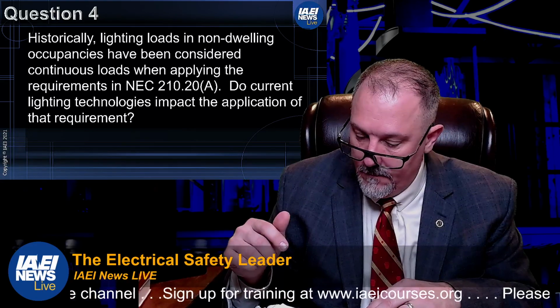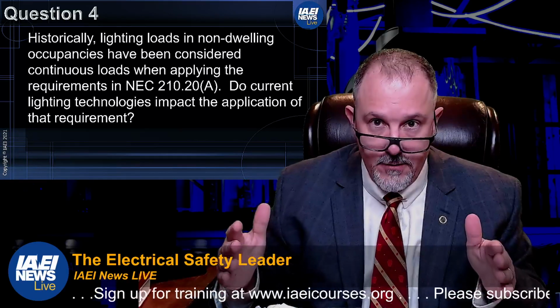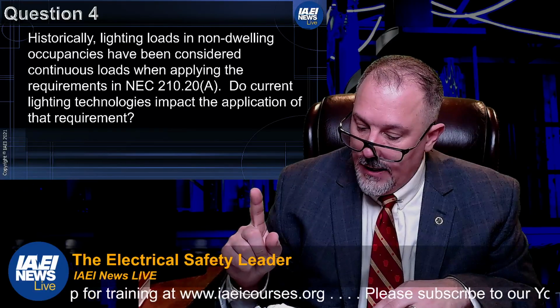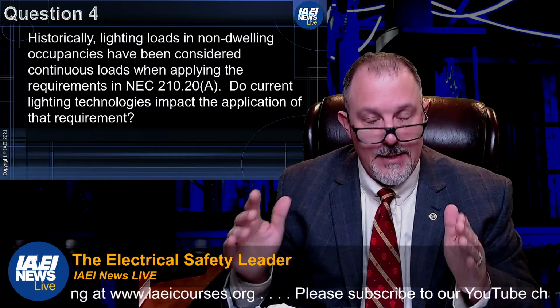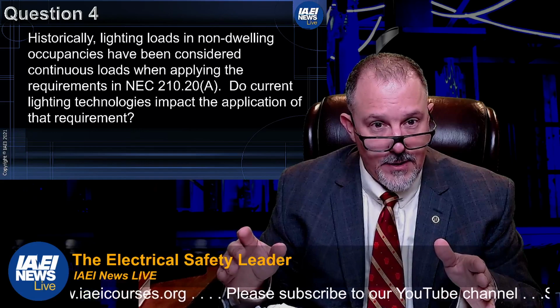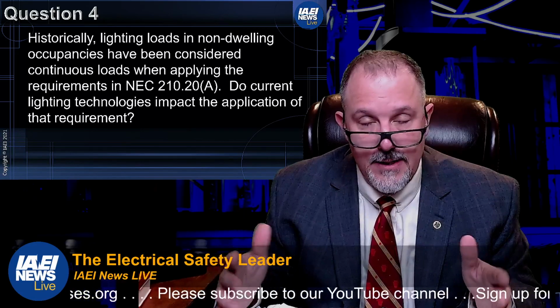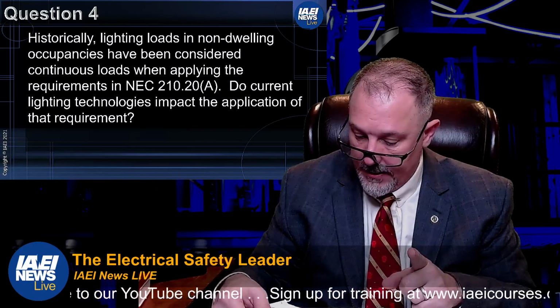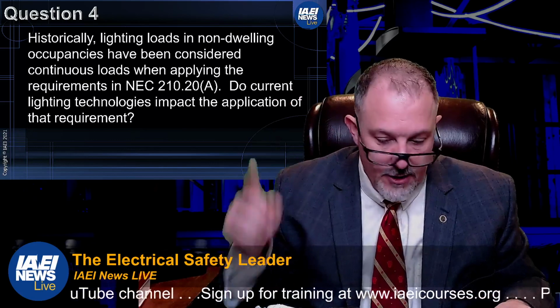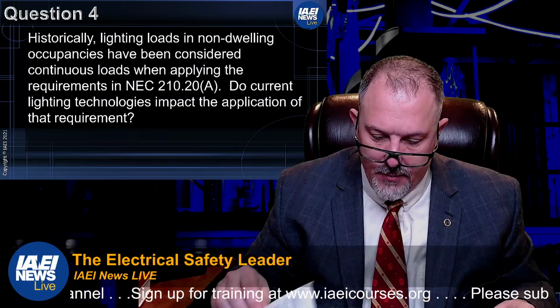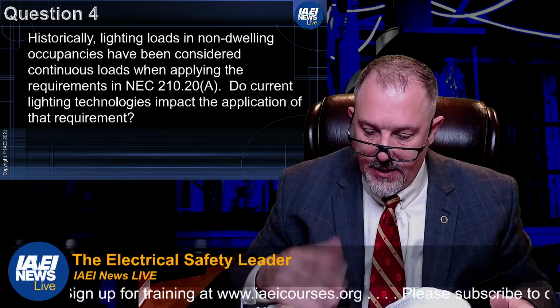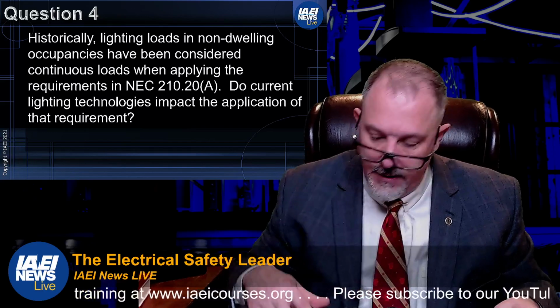So whichever one gives you the larger conductor, right? So, lighting: is lighting a continuous load or a non-continuous load? And how might technologies impact that? So I'll throw in the 210.19(A)(1) discussion, 210.20(A). Where else is this probably considered is in 215.